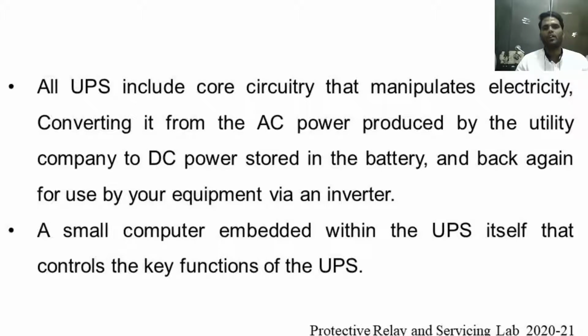So usually nowadays we are using a UPS with a microprocessor or microcontroller. It is a small computer embedded within the UPS itself that controls the key functions of the UPS. It is going to manipulate the electricity, control the rectifier power, control the inverter power like DC to AC and AC to DC, control how much power has to flow to the batteries, and monitor the load conditions. So overall my system is going to control all the parameters.